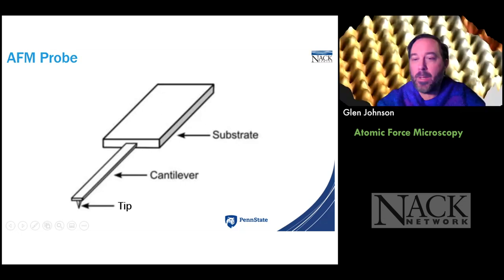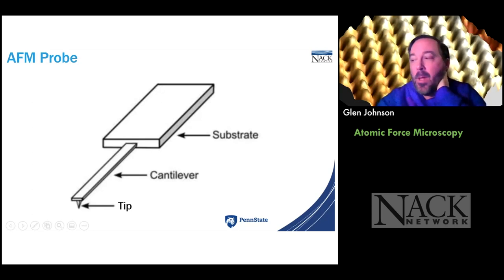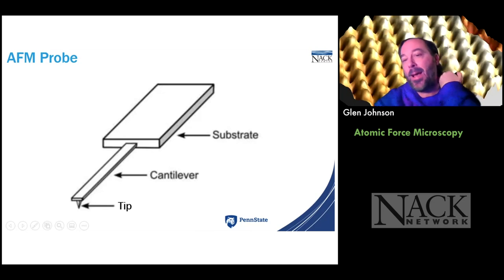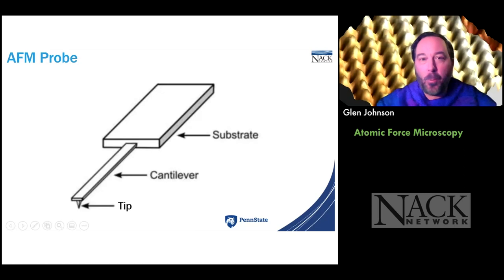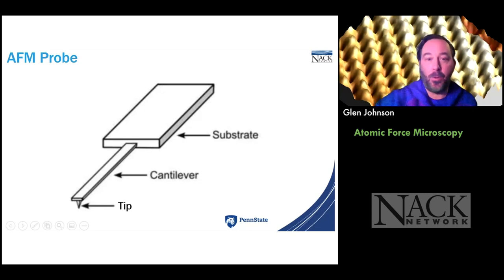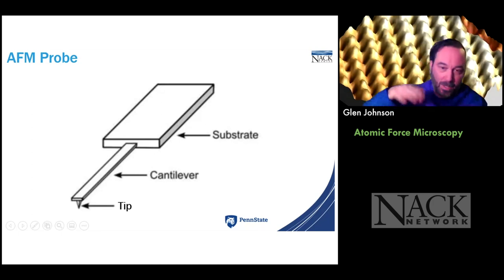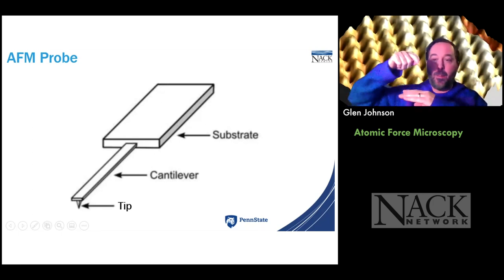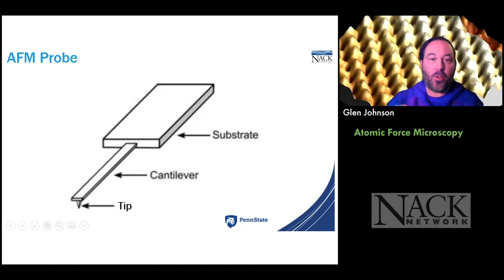We have a question: is breaking the tip a common problem? If you're not careful, it is. Another question: can you differentiate between something squishy versus something hard? Yes — there are specific modes of AFM for that, called phase imaging. It's an oscillating type of tip that bounces and can differentiate material stiffness. There's also tapping mode, where the cantilever oscillates in air and taps the sample — used for things that can break easily. And there is also a non-contact format.